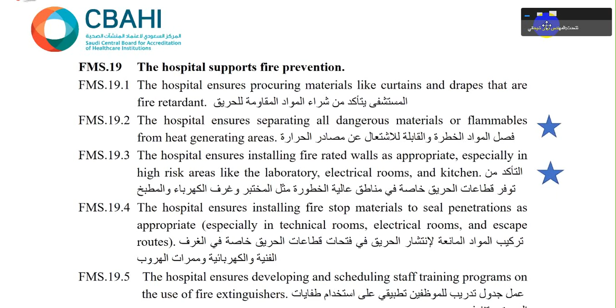We should have fire zones, with fire-rated doors around the fire zone. We should install fire stop materials in fire zones, and we should train our people how to use fire extinguishers, as mentioned before. This is an example of fire stop materials. Actually, the most popular and most famous companies are Hilti and 3M, to the best of my knowledge. Once you install it in your hospital above the fire-rated doors or in the penetration between fire zone and others, please try to have this metallic tag and install it around the fire stop materials to prove that we are installing the proper fire stop materials.